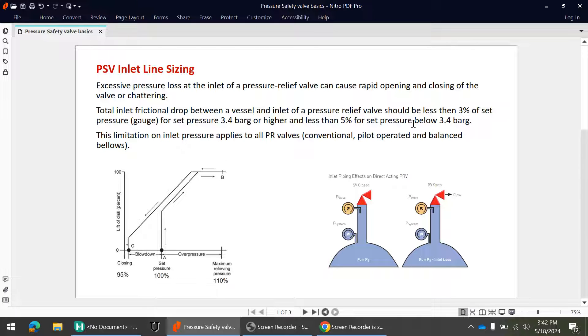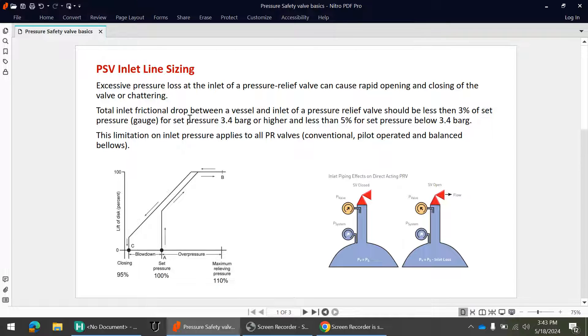This limitation of 3% of set pressure is applicable for all types of PSVs — conventional, pilot, and balanced. So for every type of PSV, this criterion applies. The inlet line pressure drop from the vessel to the PSV inlet should not exceed 3% of set pressure, and these losses are the non-recoverable frictional losses.